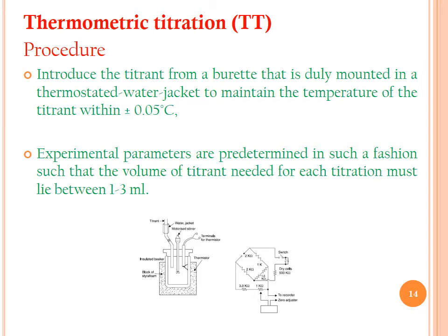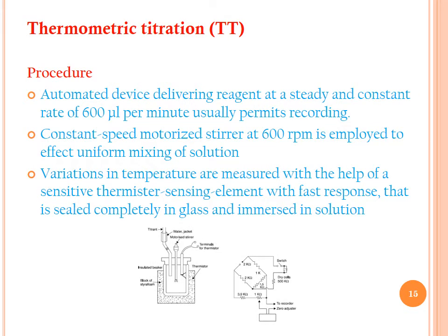The procedure: introduce the titrant from a burette duly mounted in a thermostated water jacket to maintain the titrant temperature within ±0.05°C. Experimental parameters are predetermined so that the volume of titrant needed lies between 1 and 3 mL. An automated device delivers the reagent at a steady rate of 600 µL/min. A constant-speed motorized stirrer at 600 RPM ensures uniform mixing. Temperature variations are measured with a sensitive thermistor sensing element, sealed in glass and immersed in the solution.